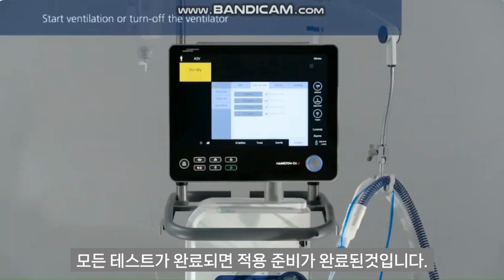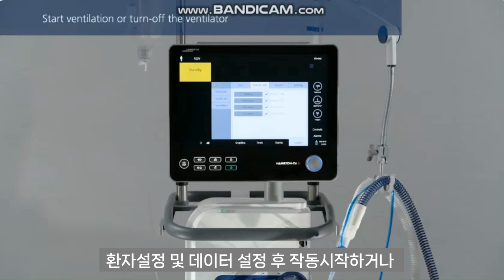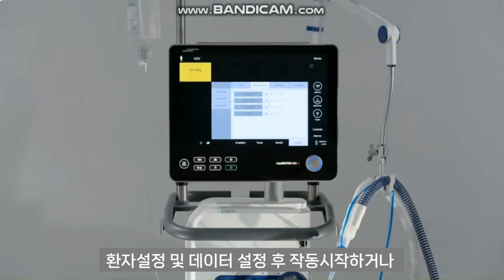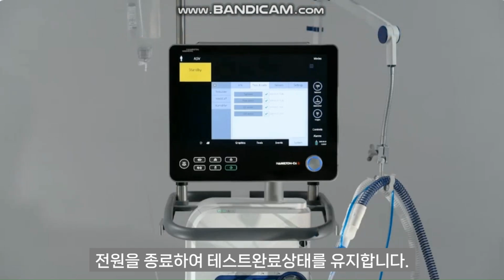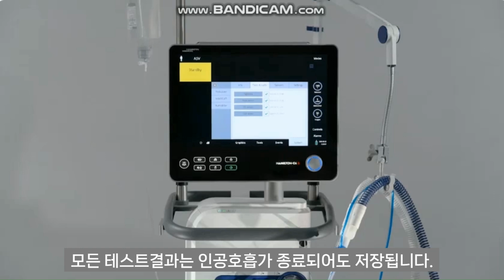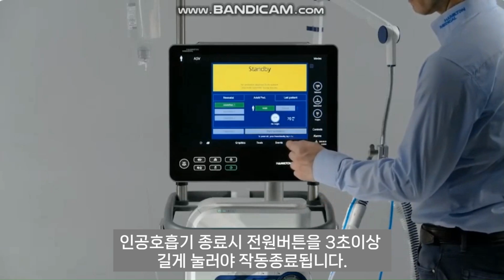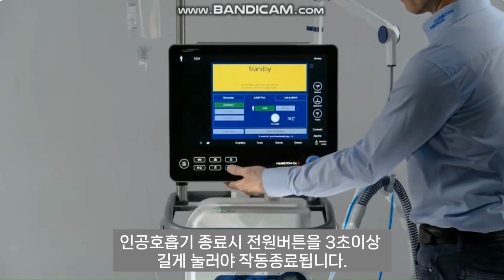Once you have completed the pre-operational checks, the ventilator is ready for use. You can set up the ventilator for a particular patient and start ventilation. Or you can turn off the ventilator and keep it stored away, ready for use. All the test results of the pre-operational checks will remain stored in the memory, even when turned off. To turn off the ventilator, press and hold the power standby key for about 3 seconds.